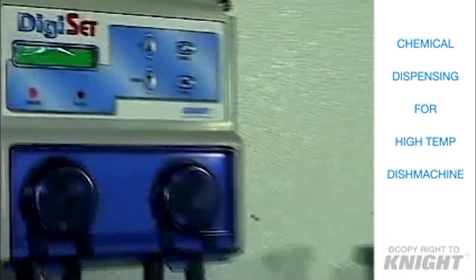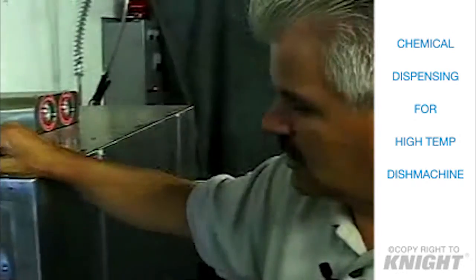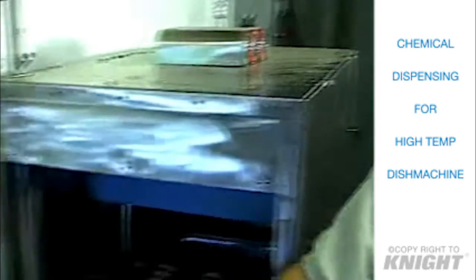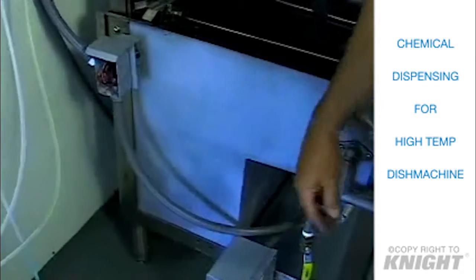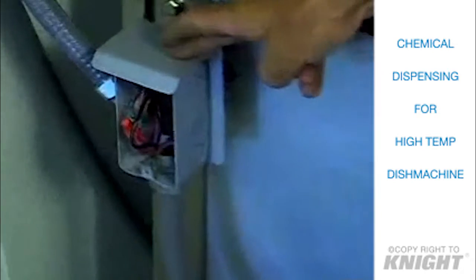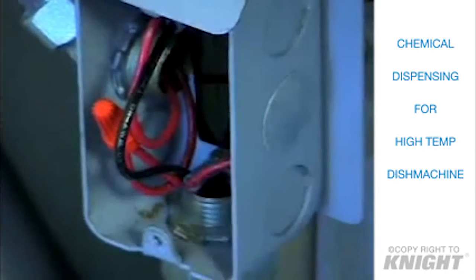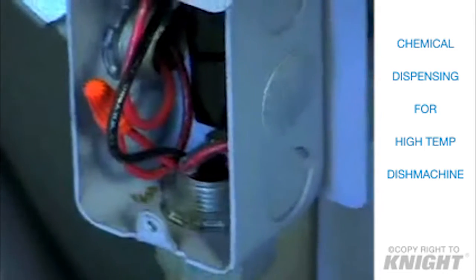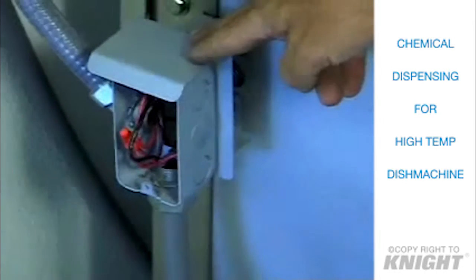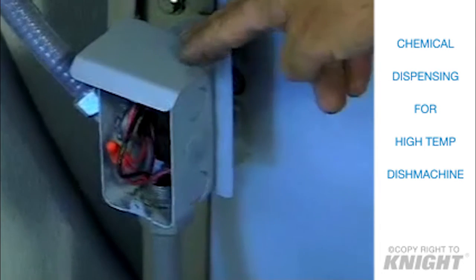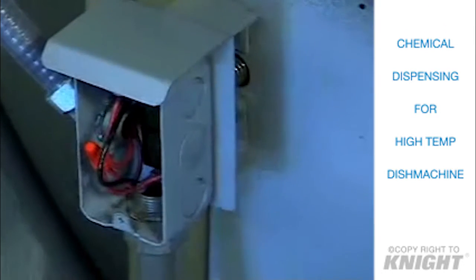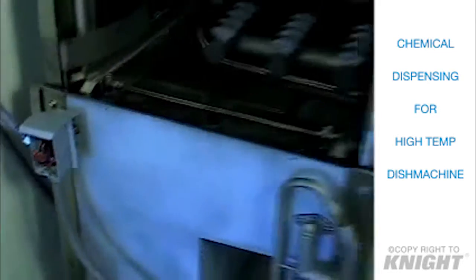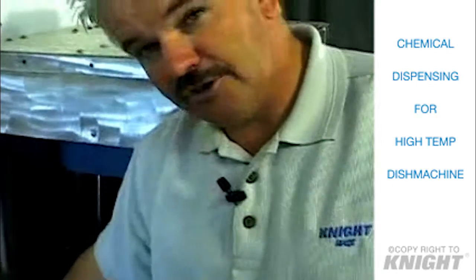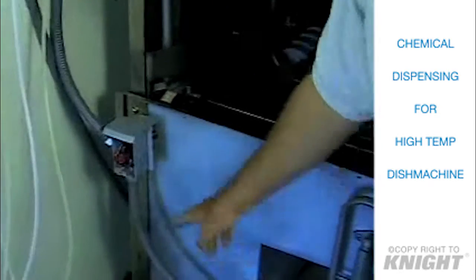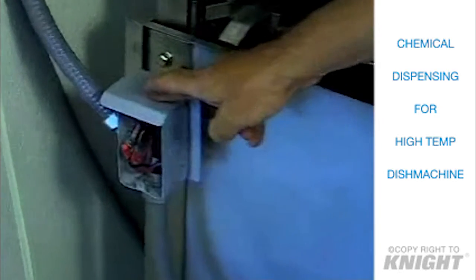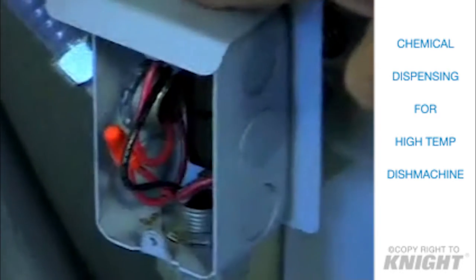And if I come down a little bit down here, you'll see to our rinse end, I've had to make a connection inside this rinse control box, and every Hobart conveyor machine has one of these rinse boxes. And inside of it, we're going to need one wire from the secondary side of this switch to control our rinse signal. Now, it was easier for me to hook it up because I don't have a table in here, and I realize it'll be a little difficult for you to get in here, but you're going to have to get in under the table to get that signal from that box because that's the only place it can come from.